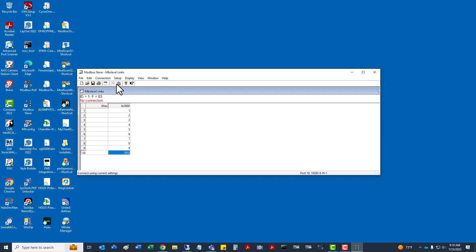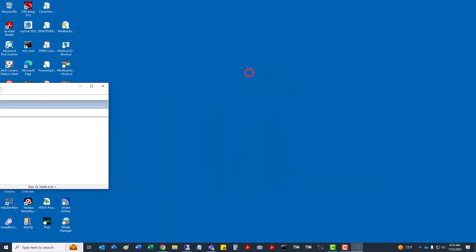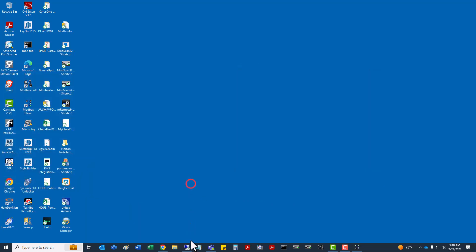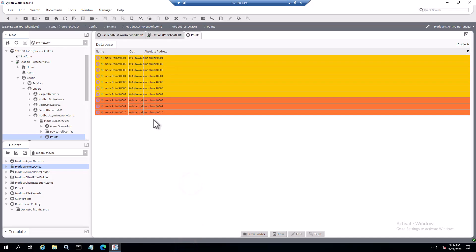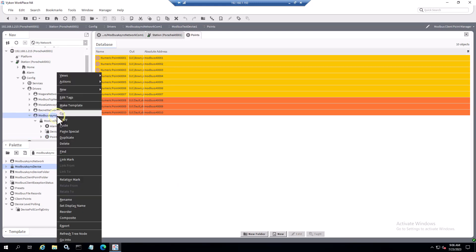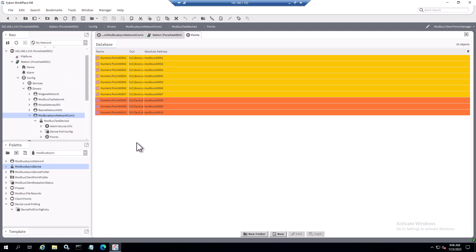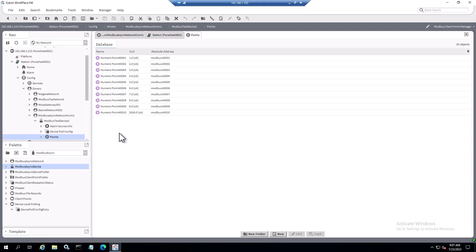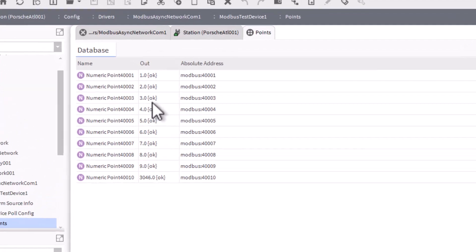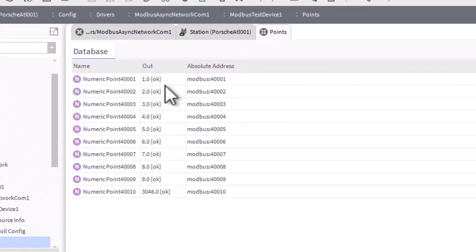Here I'm going to click connect. Now we can see that this is going out talking 19200, 8N1 and we have this data available with this last register doing the auto increment. I'm just going to drag this over to my other screen, go back and we'll look at Workbench. Here you just need to select the device, go to actions, and then left click on the ping option under actions. If everything works, we should see this clean up, and here we see all those registers are now populated. So we know that our COM port is set up and configured and there's no issues with that. I'm using the normal poll rate which is every five seconds, so here if we just watch it real quick, should see it, yep, went and updated.